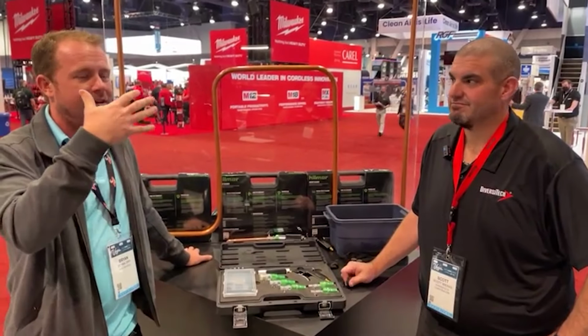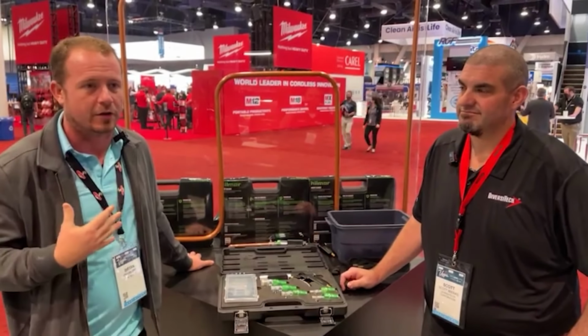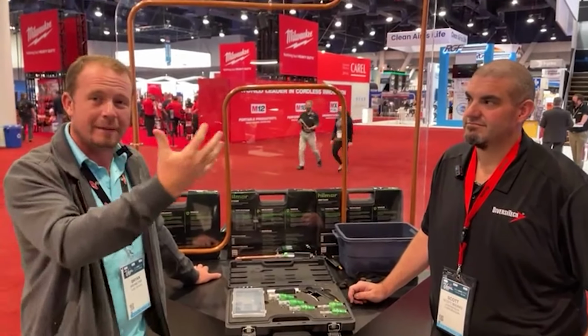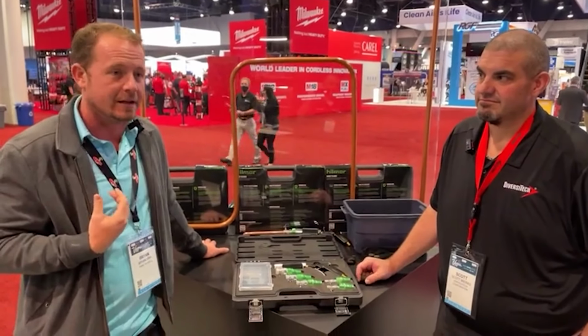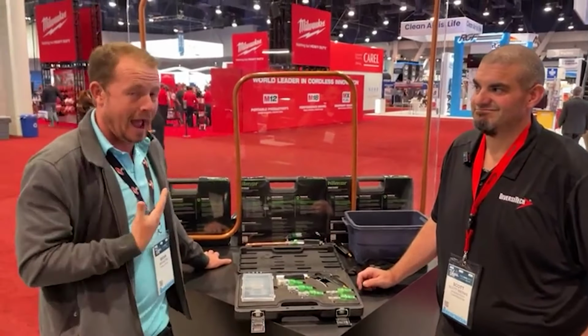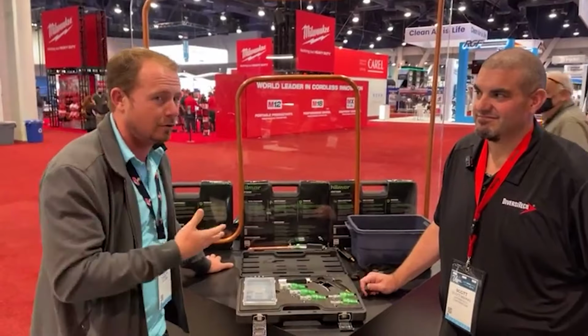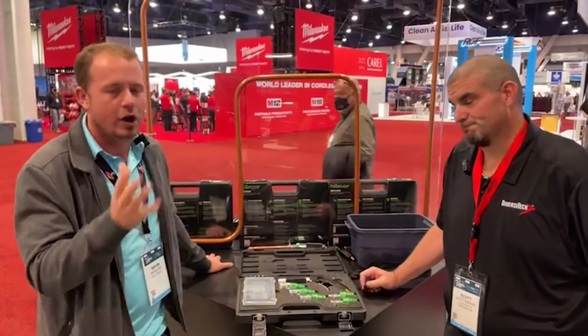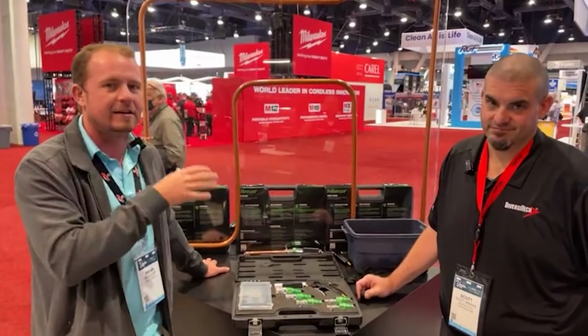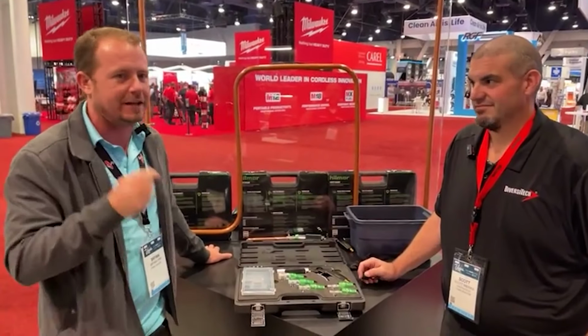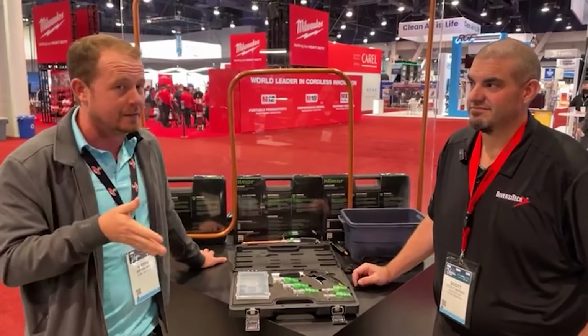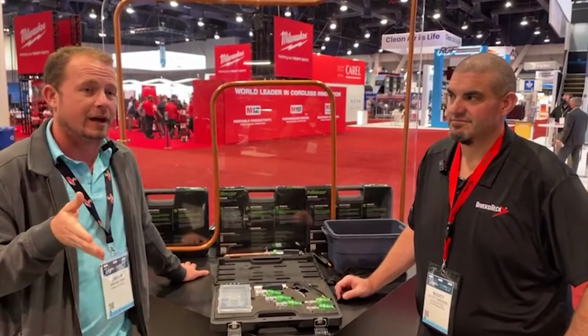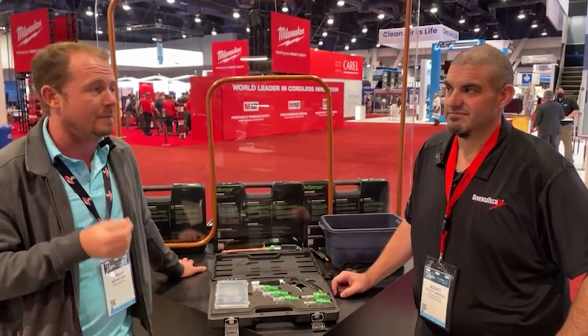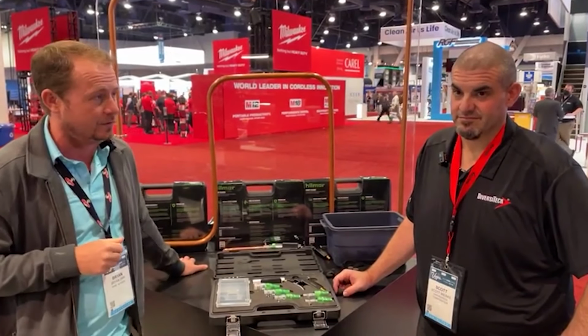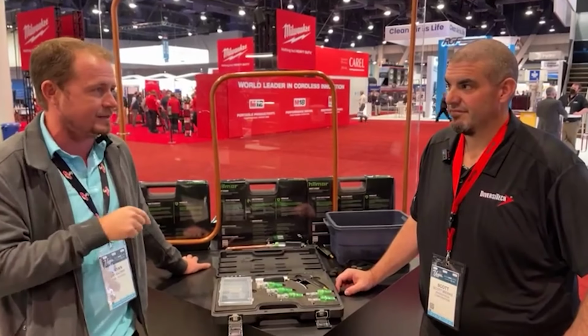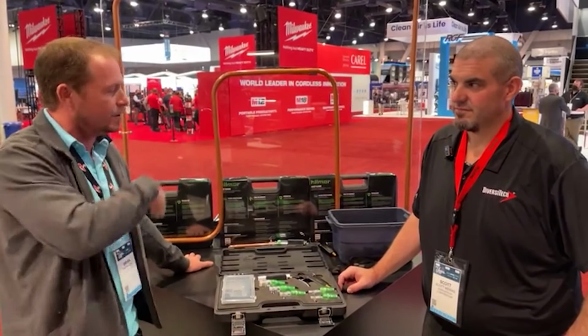We've seen a decrease in callbacks, warranty claims, all that with TXVs, compressor failures, by getting all that stuff out of the lines. Now, some people quickly ask, is this something you push through an evaporator coil, a condenser coil, a valve? Right. No, this is for a line set. This is to clean your 3/8 and your 7/8, 3/8, 3/4, and you do want to clean both lines. Even though the liquid line you would think wouldn't have a lot in it, we've been amazed at how much stuff comes out of that liquid line. We'll talk about some of the key practices after we do the demo.